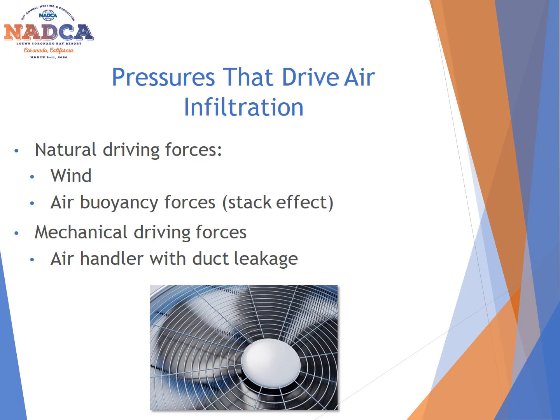The other thing that is mentioned here is stack effect. That happens even more so in taller buildings. As the air heats up, it has a tendency to rise, and as the air rises, it creates a vacuum or suction from the lower floors. This happens primarily on taller buildings. That's why if you go into a skyrise building, you'll notice there are revolving doors at the bottom, and those are in place to help reduce stack effect.